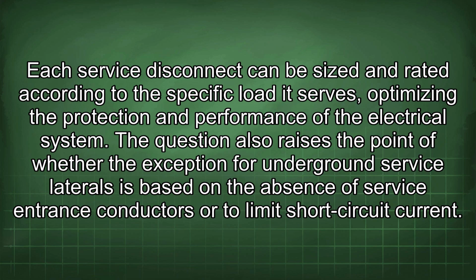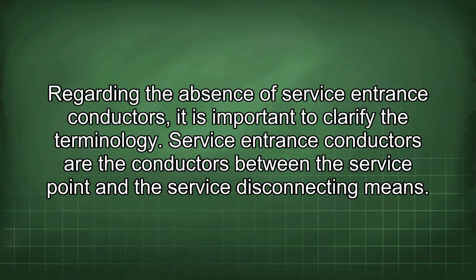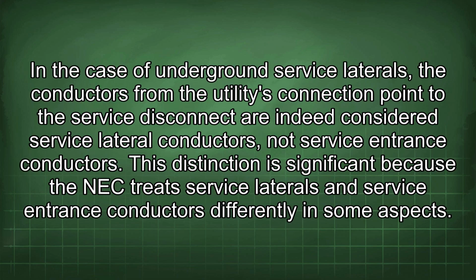The question also raises the point of whether the exception for underground service laterals is based on the absence of service entrance conductors or to limit short-circuit current. Regarding the absence of service entrance conductors, it is important to clarify the terminology. Service entrance conductors are the conductors between the service point and the service disconnecting means. In the case of underground service laterals, the conductors from the utility's connection point to the service disconnect are indeed considered service lateral conductors, not service entrance conductors.